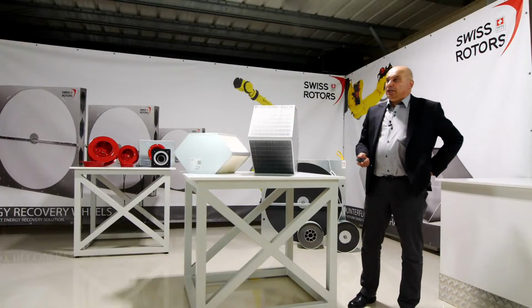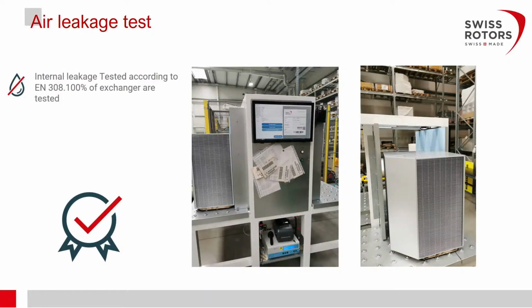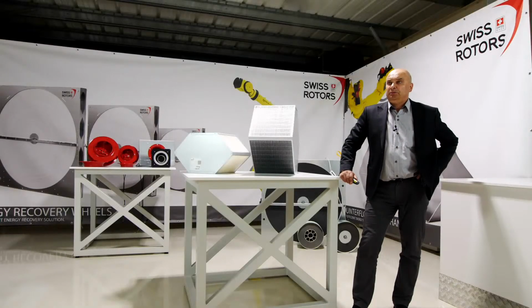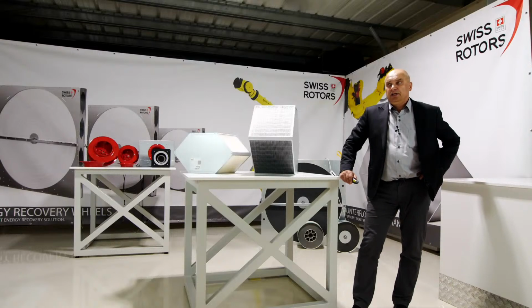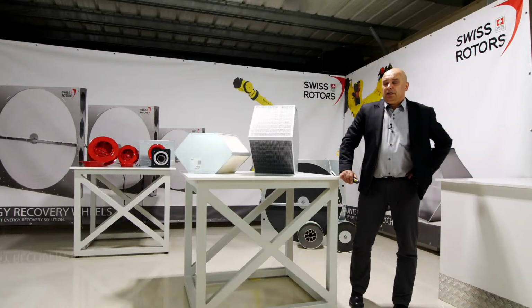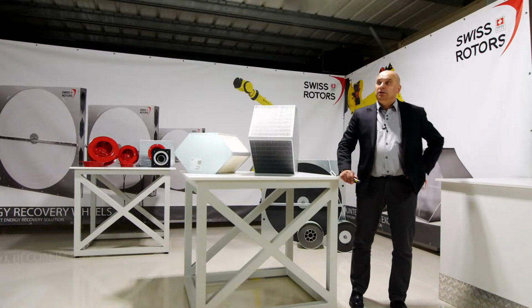Some information about the test. Each plate heat exchanger, before we release it and then start to pack, must go through the internal leakage test. This is introduced by the norm EN 308 and also some guidance from the Eurovent. So we are following those guidance, and 100% of the exchangers are tested. So we cannot print a label with the quality stamp mark if it has not passed through this test.